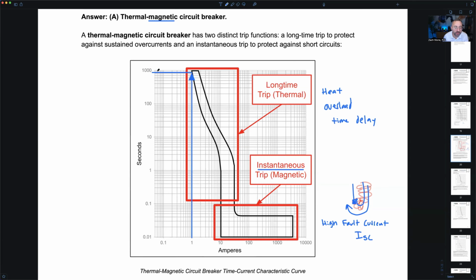So the overload region, the thermal region, it's designed to protect against gradual increases in current. Again, I worked around a lot of motors. So I think about motors in dusty environments. The fan attached to the rotor isn't as efficient anymore at cooling down the motor windings. What happens? The motor starts to draw more and more current as the motor gets hot, right? Hot temperature actually increases the load on electrical machines and drives.